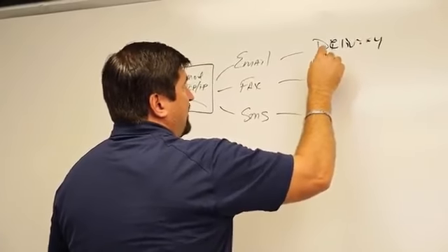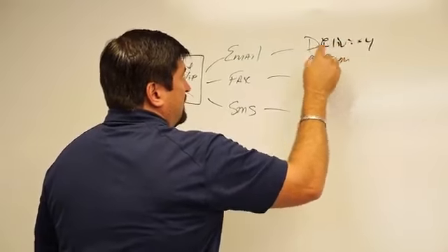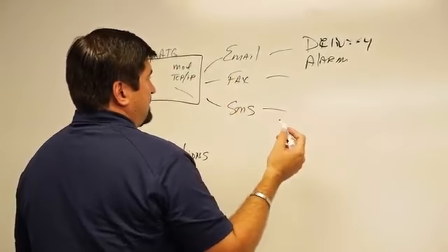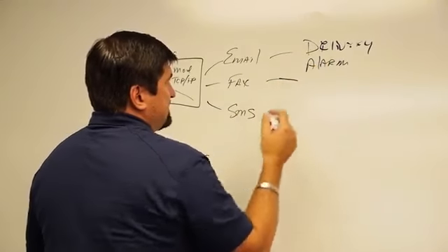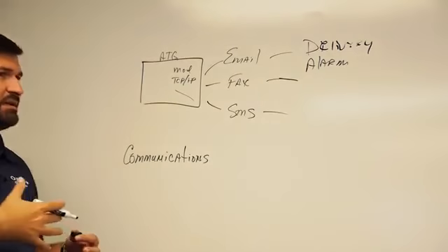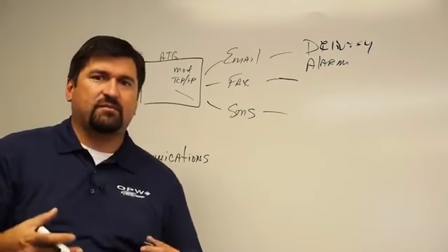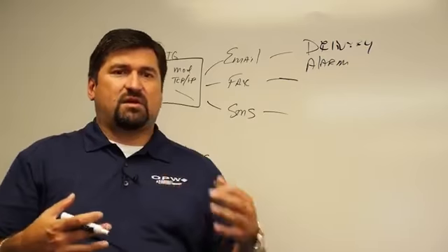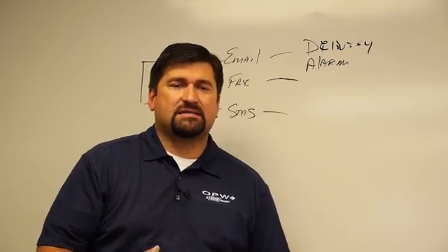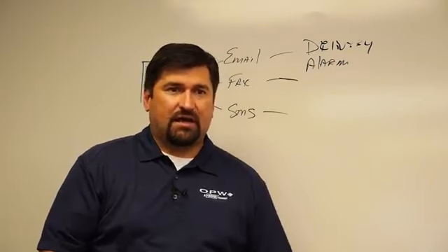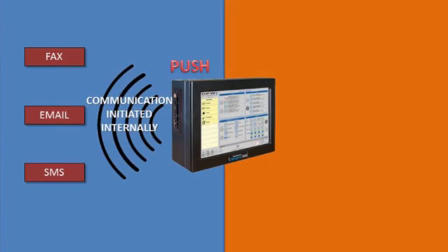Or I will have an alarm company that's monitoring if I have water or fuel in a sump. I can send the fax to the same people, but you're basically looking at external communication from the console, getting in touch with somebody when there's an event that happened at the site, whether I need product now, or I've got water in my tanks, I've got fuel in an STP sump. It's pushing that data outside from the console to let somebody know at the home office or somewhere that they can dispatch somebody out to take care of the problem.